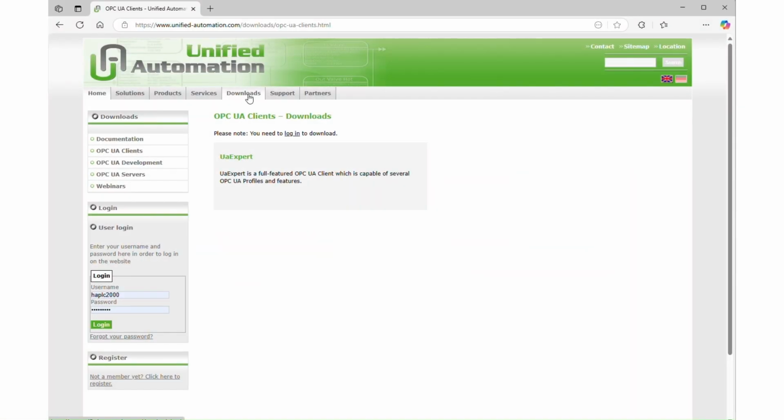The UA Expert is a full-featured OPC UA client toolkit framework provided by Unified Automation Studio, supporting features like data access, alarms and conditions, historical access and calling of UA methods. In our case, the main purpose of using UA Expert is to read node values in devices connected at the same time to the smart communication card.